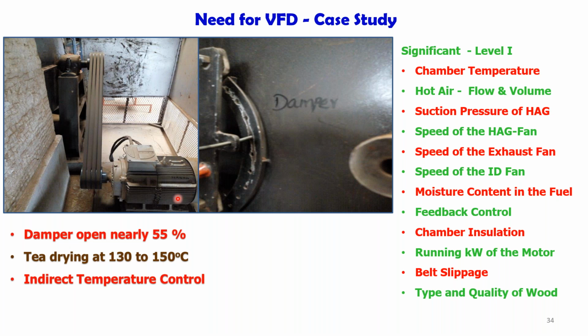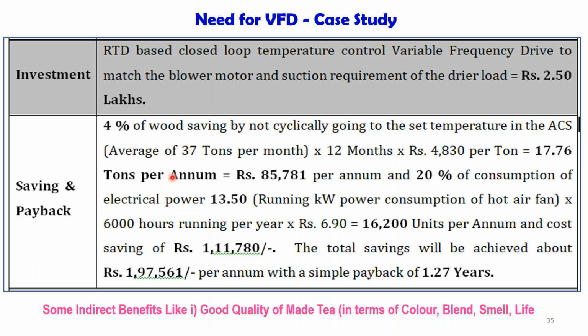So the feedback is given to the motor with the help of a VFD, and then automatically the speed of the VFD is going to be a variable one. Now, when you retrofit an existing motor and existing blower with a closed loop VFD, there are two benefits available. Number one, you can also save the wood. We are expressing that it's going to be a 4% wood saving, and also a saving of 20% of the energy consumption. So put together, there's a saving of almost 2 lakh rupees, and the retrofitting arrangement will cost around 2.5 lakh rupees.